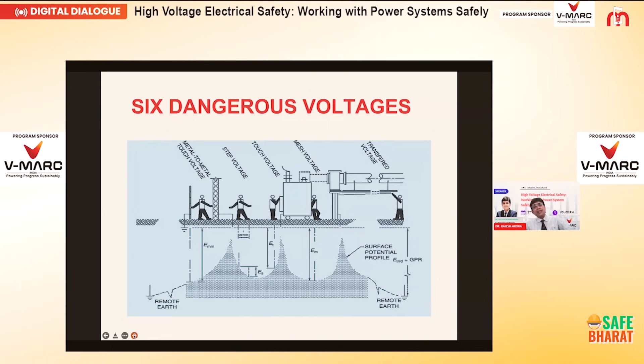Then you have to understand why I am talking about earthing and grounding, because I want that fault current back to the source - because I need to protect the living beings in the vicinity of my substation. I need the proper functioning of the protection system I already installed, and I have to limit the touch and step potential within tolerable limits.